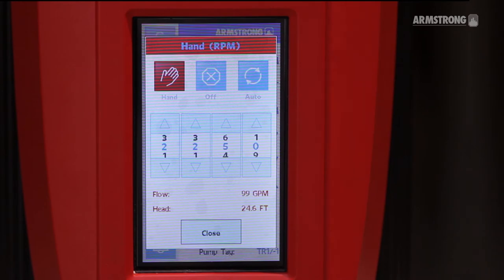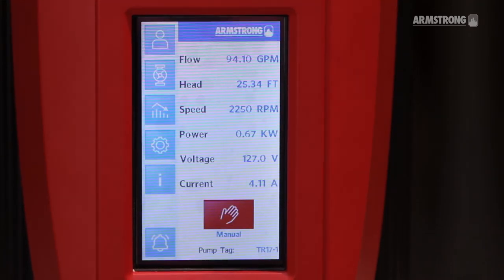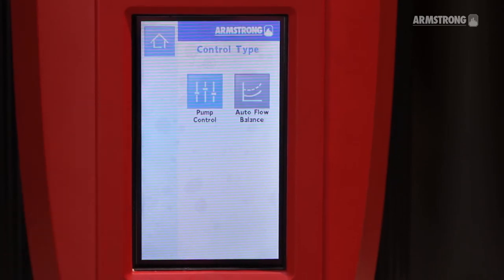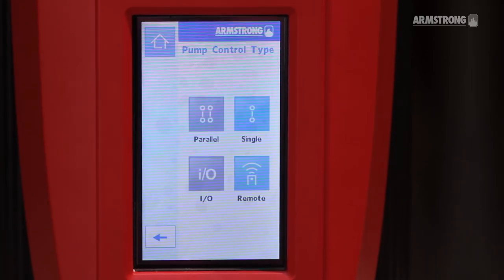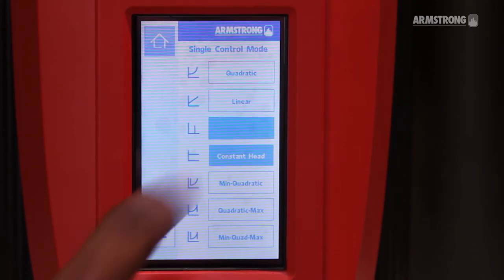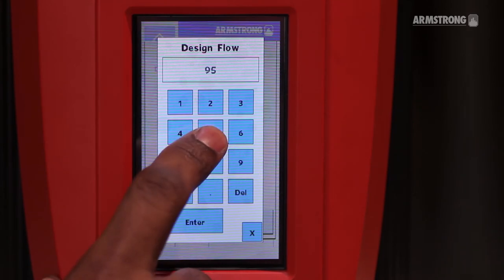After confirming it can maintain that flow, click on Pump Configuration, Pump Control, Single, Constant Flow. Enter the desired flow set point: 95 GPM.